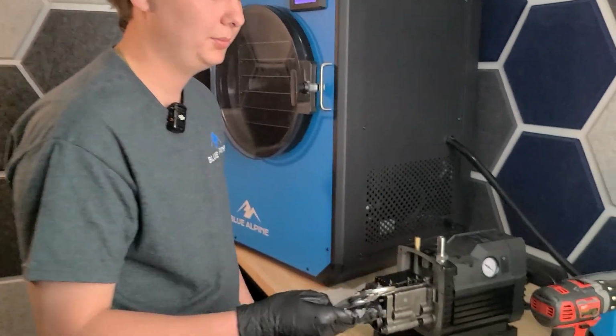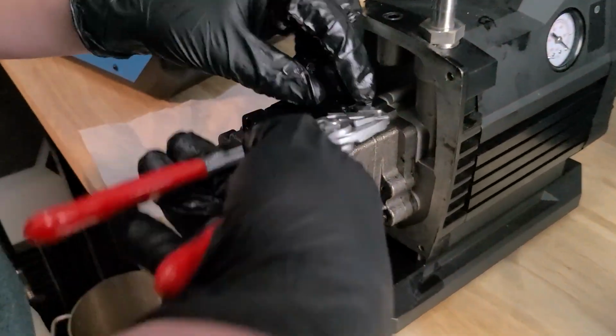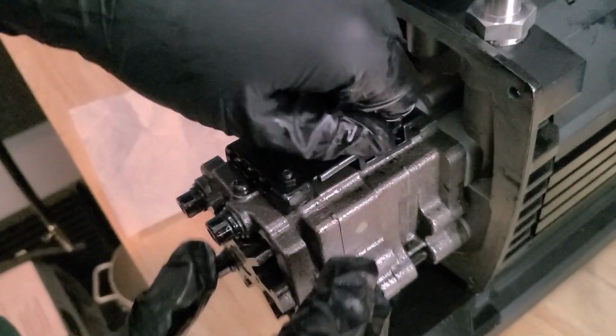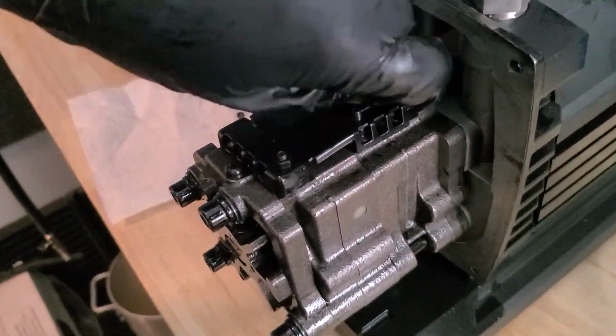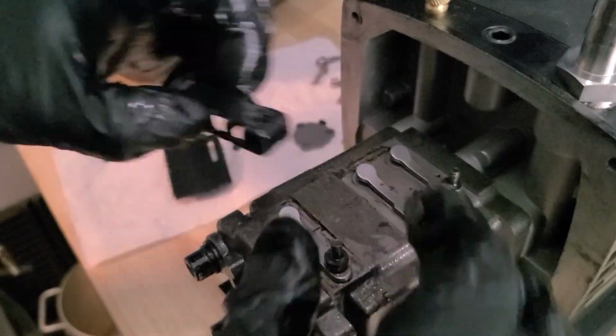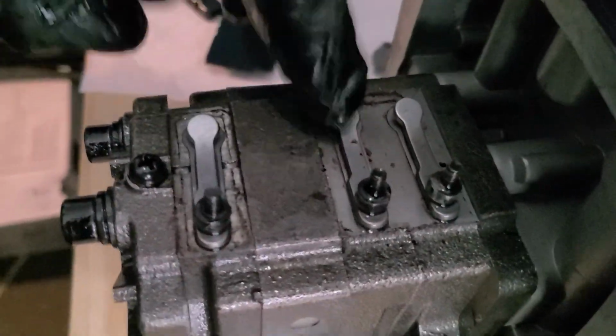Next, we're going to check your reed valves on your vacuum pump. So to start, you're going to want to take your pliers and take off these nuts that are holding down this piece of plastic that is covering the reed valves. Next step is to pull off the covers. It will expose your 3 reed valves. This is the first, second, and third.